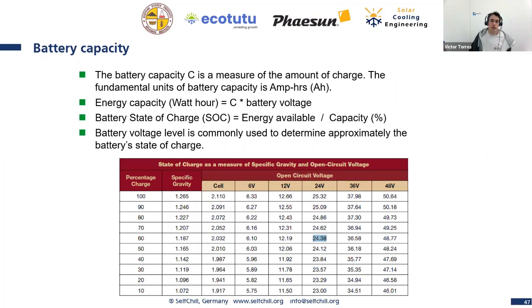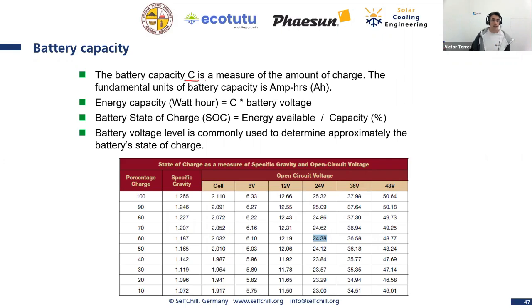Most of you know how to measure battery capacity, but for those not familiar: battery capacity is defined in ampere hours. So if we have a battery with 100 ampere hours, it will deliver 1 ampere for 100 hours, or 100 amperes for 1 hour. That's how batteries are defined by capacity, but the energy capacity we normally want in watt hours, so we multiply the ampere hours by the battery voltage.